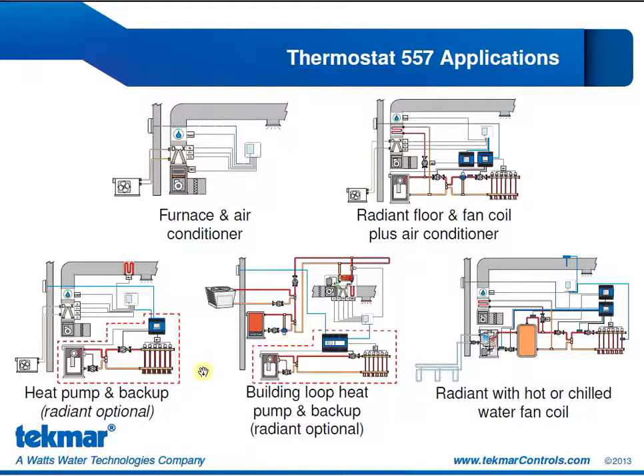Our second heat pump application features a building loop heat pump. So we have a loop throughout the building that's maintained within a certain temperature range from a boiler and a cooling tower. And in individual units of the building, there are water-to-air heat pumps. Again, we have the option of the radiant floor. That's why it's outlined in the dashed red line. If we include the radiant, that's our first stage of heat. Our heat pump will provide a 2nd and 3rd stage of heat, and a 4th stage of heat is possible with the electric strip backup. When we switch over to cooling mode, we have up to 2 stages of cooling from the heat pump.